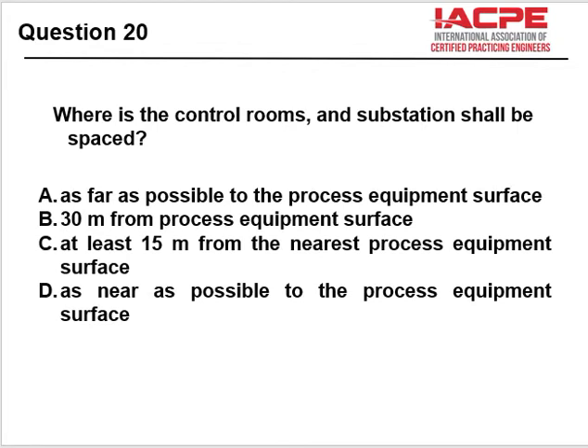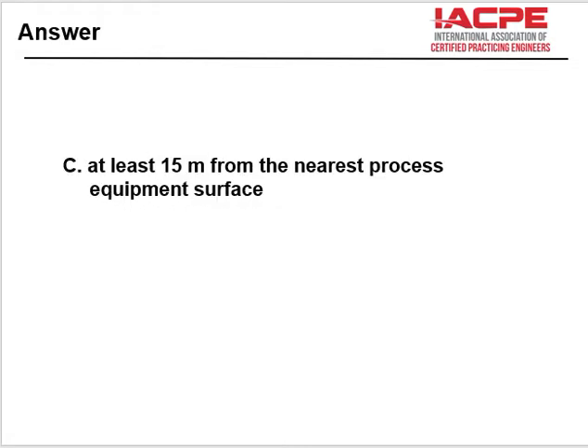Where are the control rooms and substations to be spaced? Control rooms that have people occupancy, you have to do a facility siting study, and if they're very close, you have to have them be a blast-proof building. As far as possible, 30 meters, 15 meters, as near as possible, at least 15 meters from the nearest process equipment.